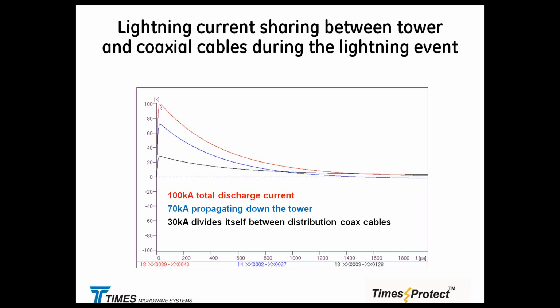Anyway, let's assume a 100 kiloampere strike, which is pretty massive from what you remember looking at the distribution graph. If 70 kiloamperes go down the tower, the remaining 30 kiloamperes will divide among all of the other service cables coming down from the antennas to the shelter. Take a very basic tower, three sectors, two antennas per sector, six cables total. Dividing the 30 kA among six cables, mathematically you are looking at around 5 kiloamperes per cable. Remember that 60 to 70% of the current will go on the shield, and around 30% will go on the center pin. So you can figure out pretty quickly how this divides itself.